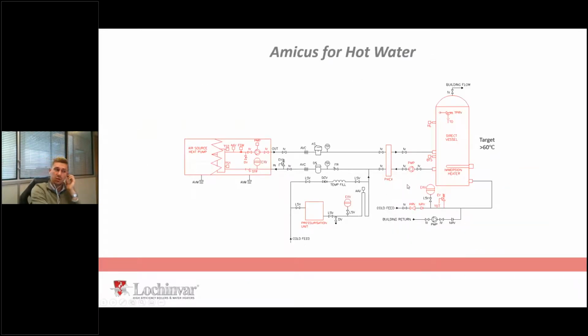And what we do. So electric air source heat pump. And what it does is it monitors a tank temperature sensor. And that tank temperature sensor this time is set to 60 degrees centigrade because we want to make sure that the system is running at a temperature which is appropriate so that we don't end up with any bugs, Legionella in the system, anything like that. And we satisfy our public health engineers because, of course, the minimum target temperature you'd be expecting is 60.